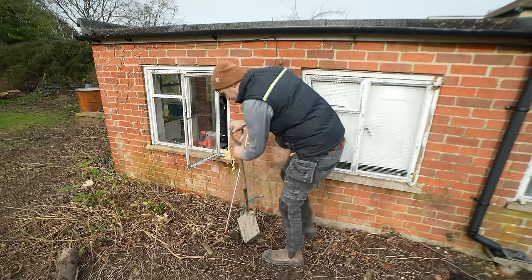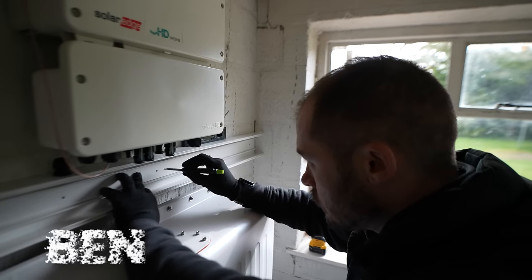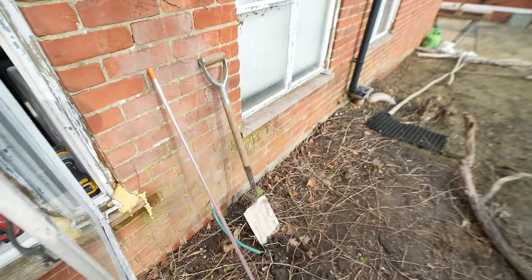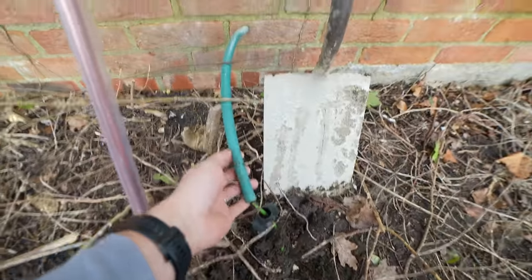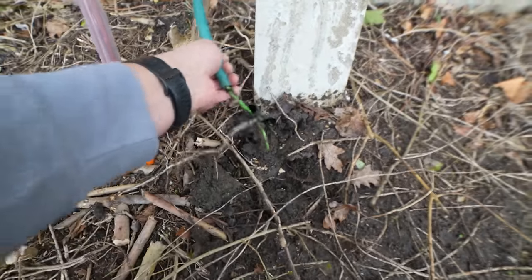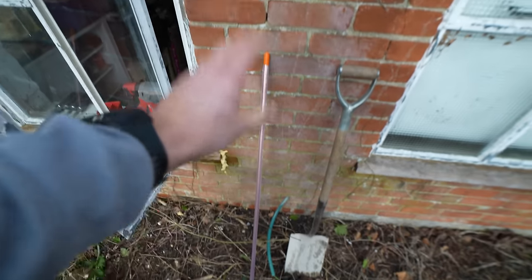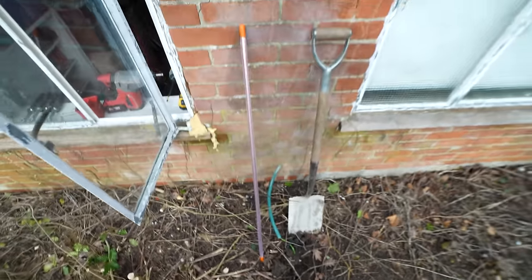What I'm doing here — let's say hello to Ben. Ben is fitting the SolarEdge gateway and battery. The gateway is going inside of there. But because this house has the potential to be going off-grid, we need an earth rod. Now what's interesting is there is already an earth rod installed here. I'm just testing this out to see if it's good enough — I don't think it is good enough. So I have another earth rod that I'm going to connect in. I'm not going to disconnect the existing one — I'm going to connect them both together in parallel.